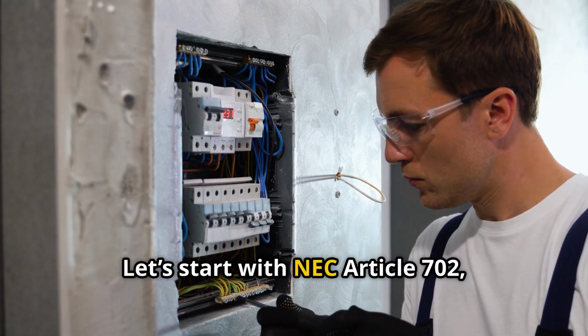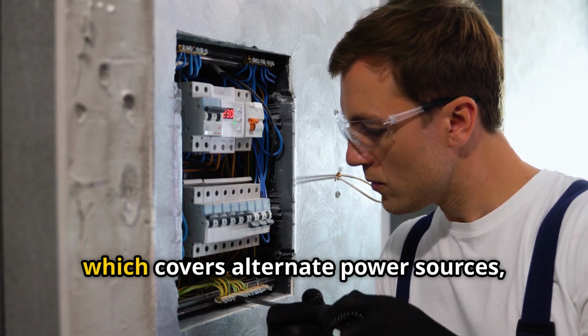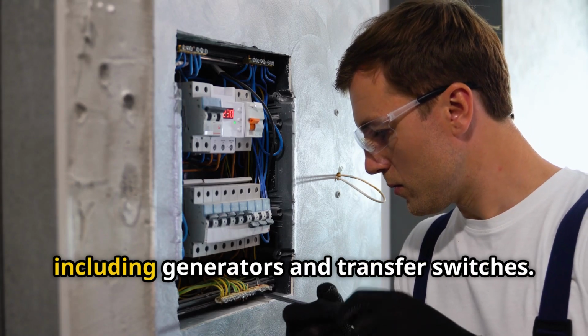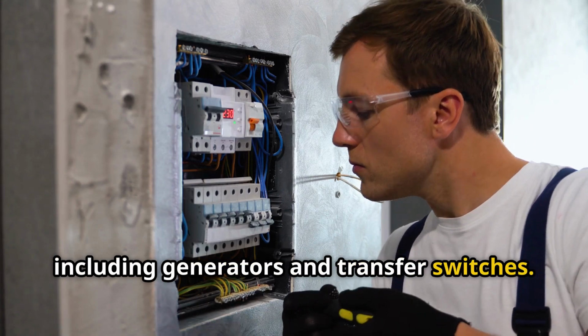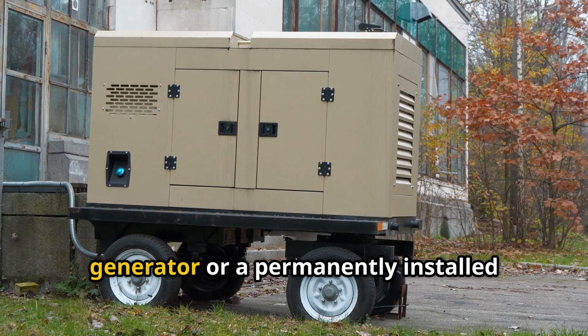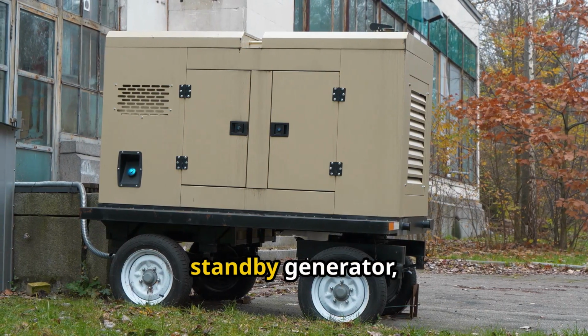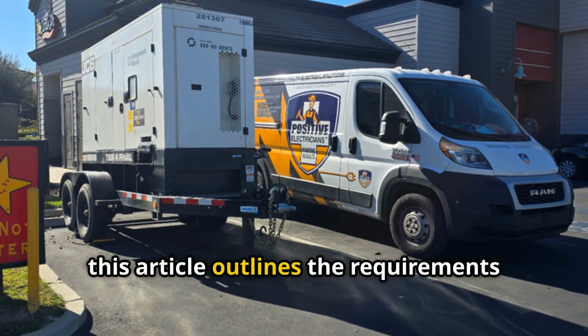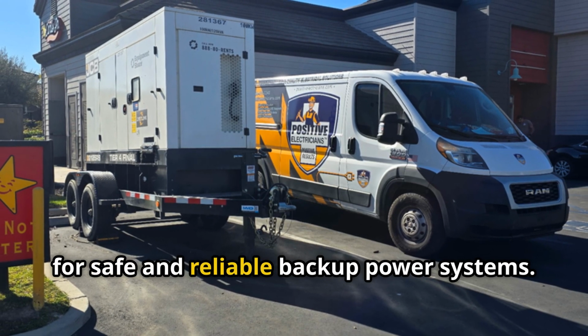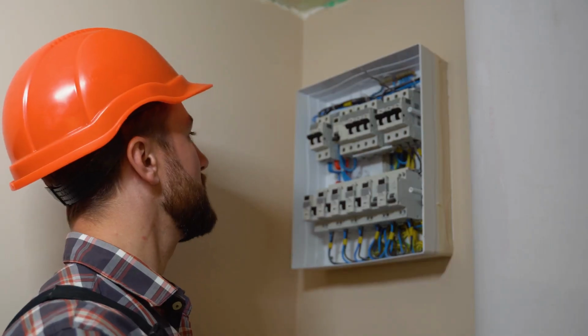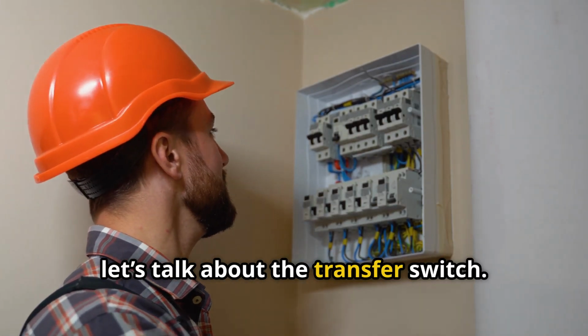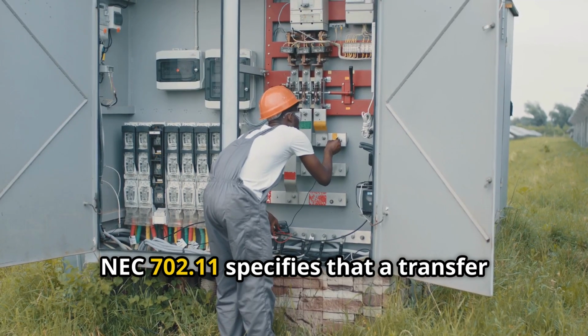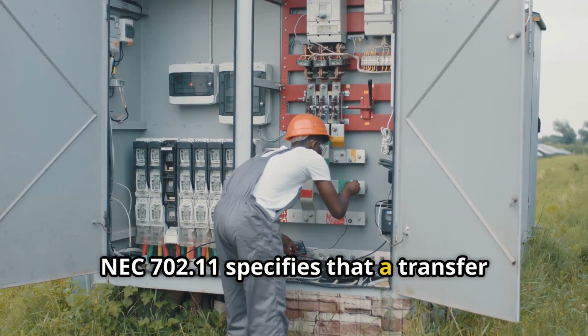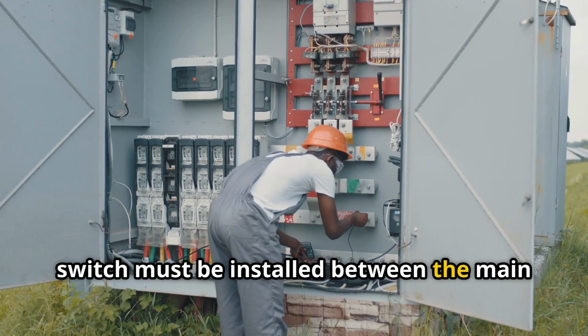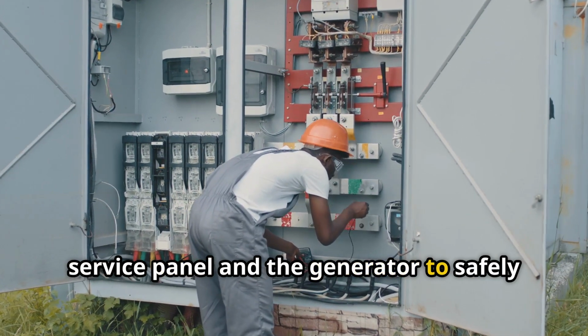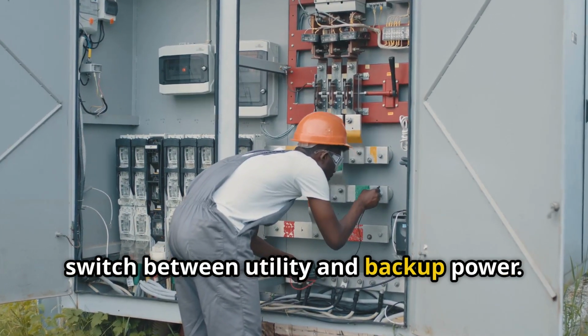Let's start with NEC Article 702, which covers alternate power sources including generators and transfer switches. Whether you're installing a portable generator or a permanently installed standby generator, this article outlines the requirements for safe and reliable backup power systems. First, let's talk about the transfer switch. NEC 702.11 specifies that a transfer switch must be installed between the main service panel and the generator to safely switch between utility and backup power.